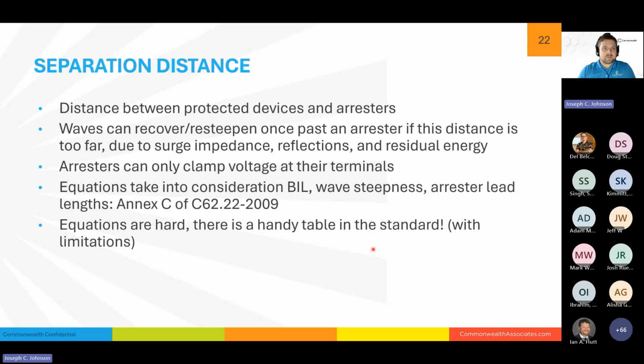So one thing about these arresters as well is the separation distance. The distance between your protected equipment and your arrestor does matter. But these waves are, again, like I said, chaotic. They have a lot of energy behind them. There are attenuations, reflections, surge impedances, all these different things come together, and they can effectively allow a wave to re-steepen and recover once it's past the arrestor, because the arrestor is only clamping its voltage at its own terminals. Once it's past, the wave starts to change back into its former glory sometimes. And if you're too far away, that wave has too much physical distance to actually reform, and it can now exceed the insulation at your equipment.